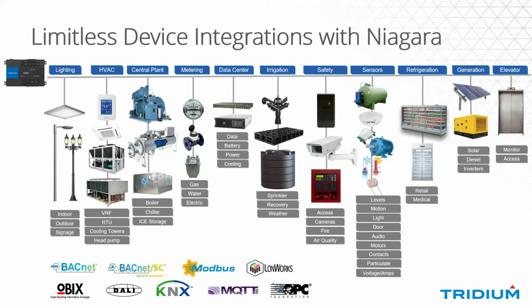So we have a very broad support of protocols, and that comes down to what software drivers are installed on the Jace, on the Supervisor. There are many drivers available within the Niagara marketplace already, or can be created if one needs to be - legacy protocols like N2 or LonWorks, all the way through to cutting edge stuff like BACnet SC.